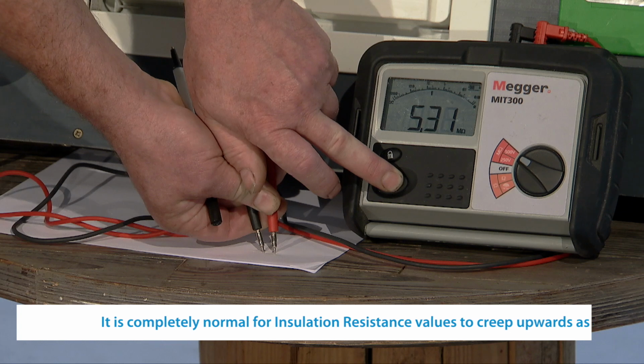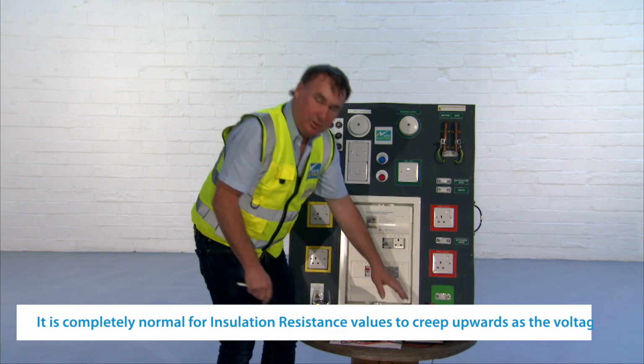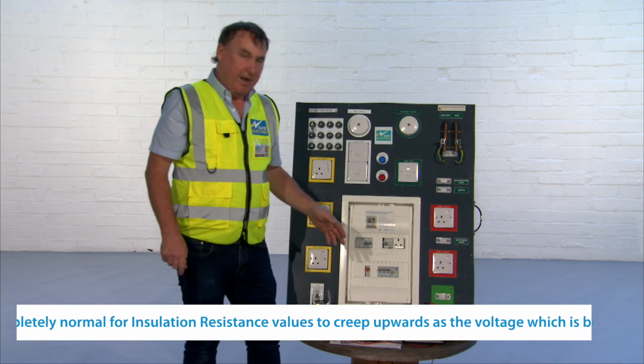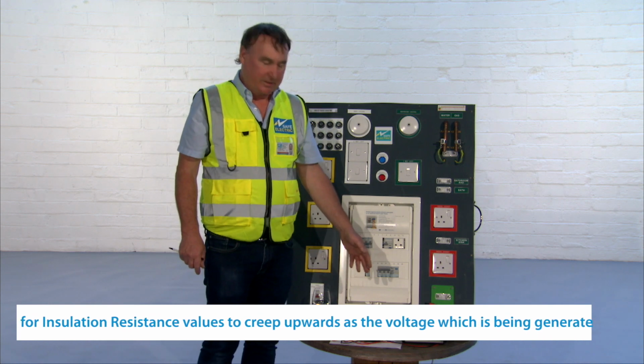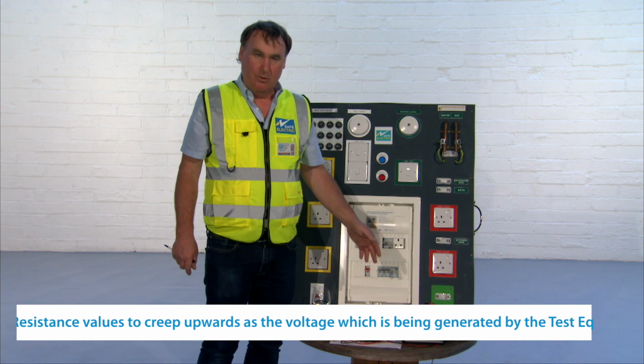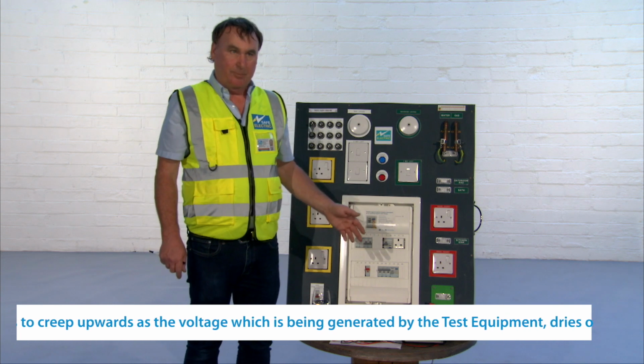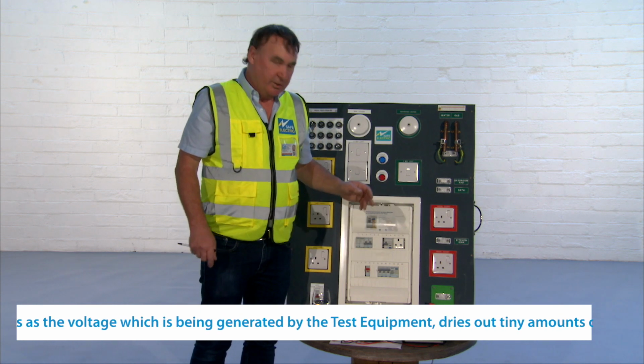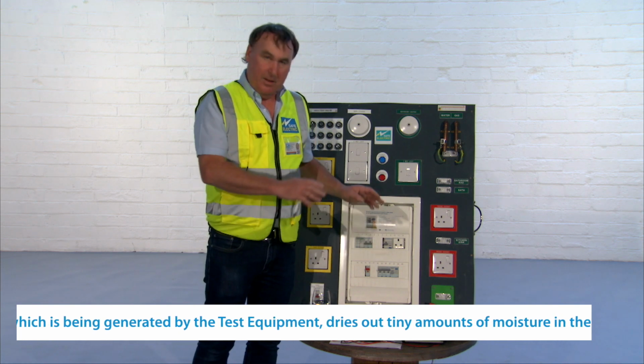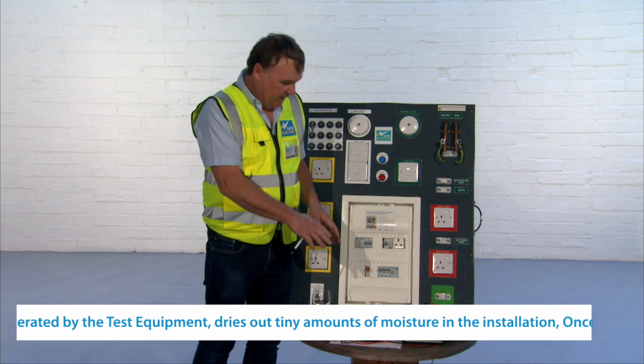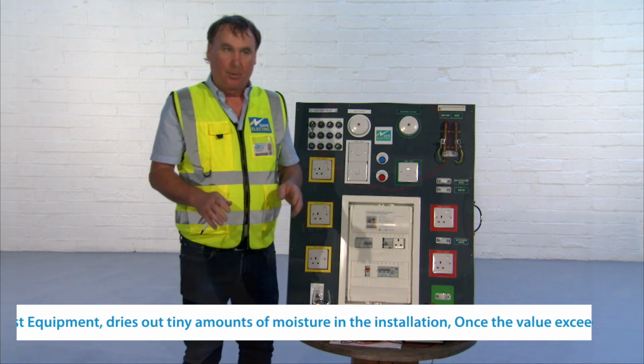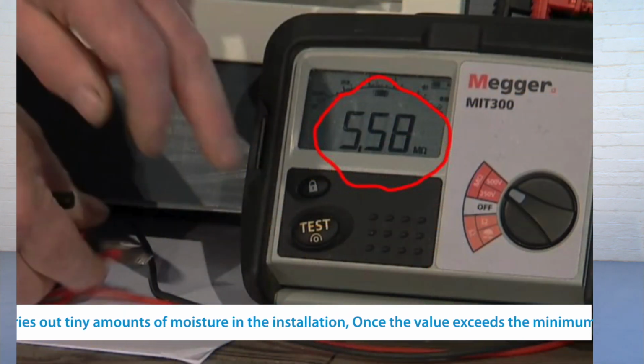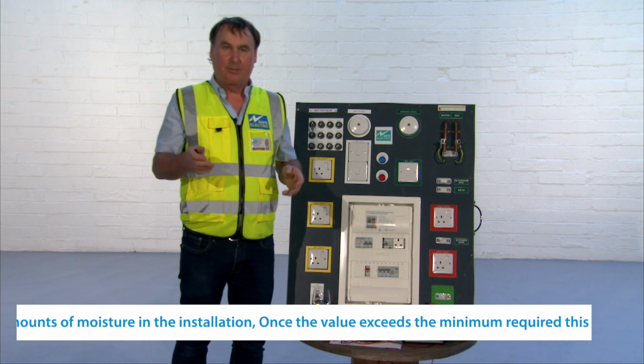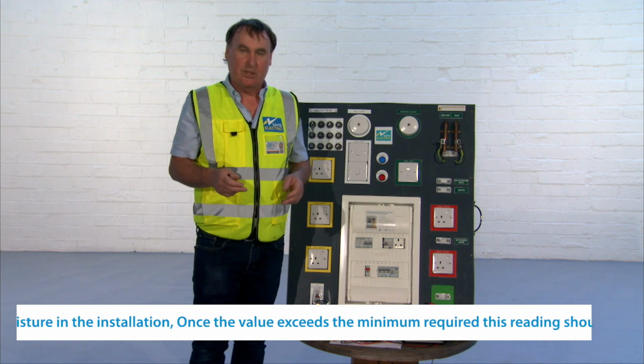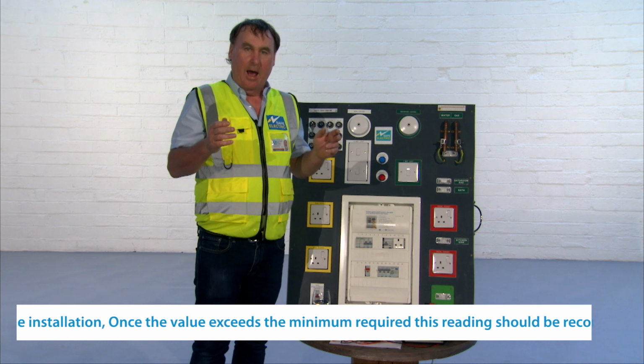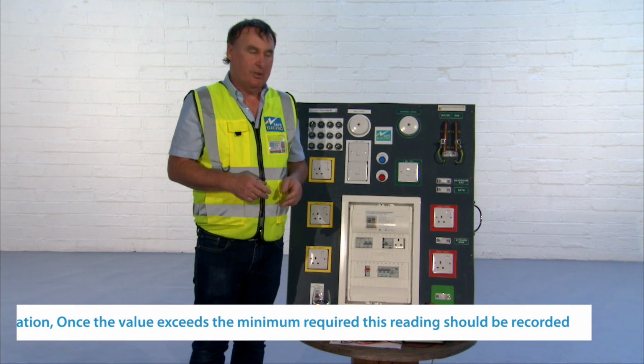And the reason it's rising is the voltage from our test meter is drying out the tiny amount of moisture that's on this piece of paper. And this will continue to rise indefinitely till it gets back to 300 mega ohms. There is no point in you wasting your time waiting till this gets to 300 mega ohms. The reading here at the moment is 5.59 mega ohms, which is a perfectly acceptable value of insulation resistance. And we should now write that on our test record sheet. Thank you.